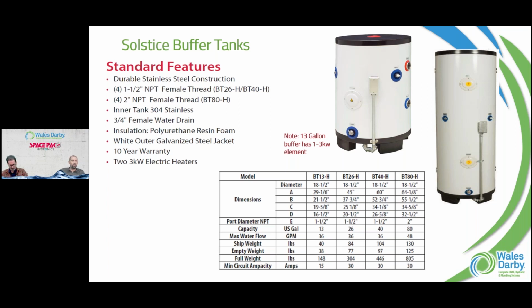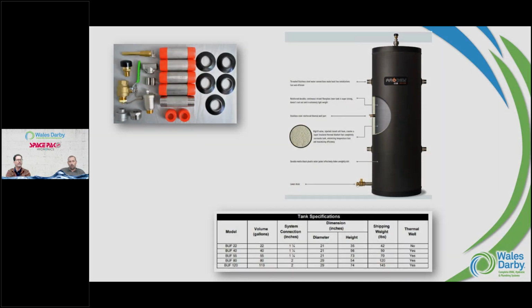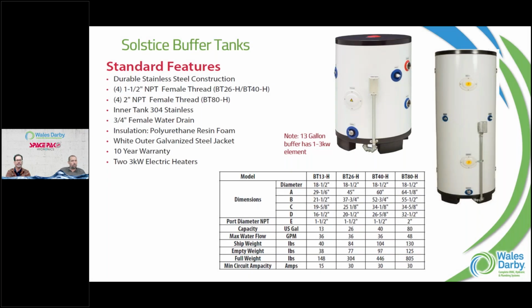Yeah, if you're losing that on the heat pump side, maybe because of outdoor temp or the glycol, maybe that's my boost, right? So what do you say, 6 kW? Yeah, 6 kW, 20,500, call it, 478. Oh, perfect. Yeah. Keep it there. 1 kW is 3413, so you do the math, 6 times 3413, you come up with 20,478. So this was our offering through SpacePak, obviously. This is something to keep that system SpacePak all the way throughout.